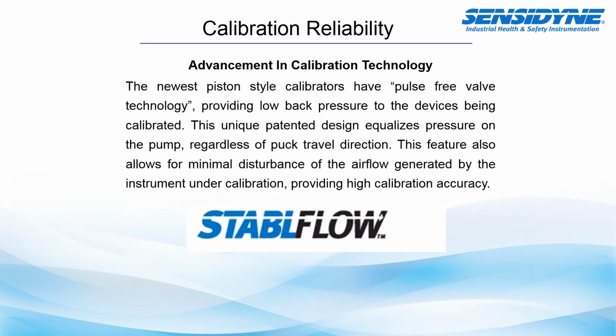Now, the newest piston-style calibrators have pulse-free valve technology. This can provide a low back pressure to the devices being calibrated. Now, this is specific to a Sensidyne product where you see StablFlow. This is part of Sensidyne's newest release, the Calibrator 3. This unique patented design will equalize the pressure on the pump regardless of the puck travel direction.